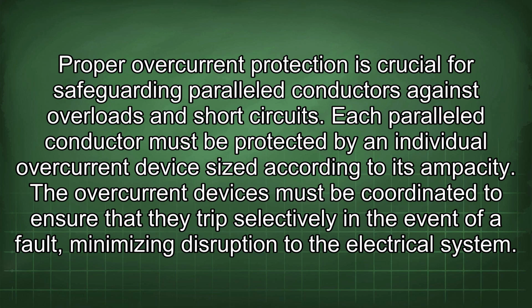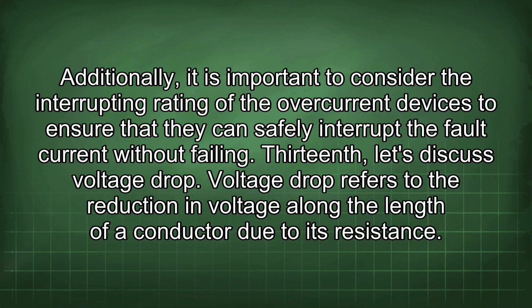Each parallel conductor must be protected by an individual overcurrent device sized according to its ampacity. The overcurrent devices must be coordinated to ensure that they trip selectively in the event of a fault, minimizing disruption to the electrical system. Additionally, it is important to consider the interrupting rating of the overcurrent devices to ensure that they can safely interrupt the fault current without failing.